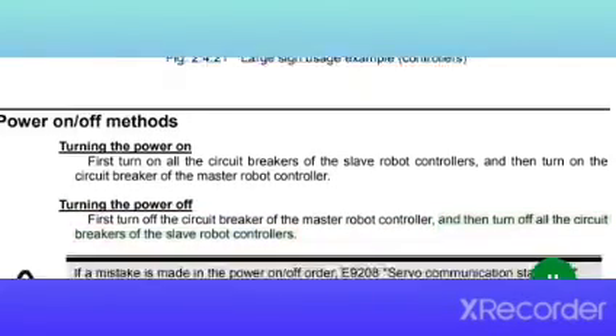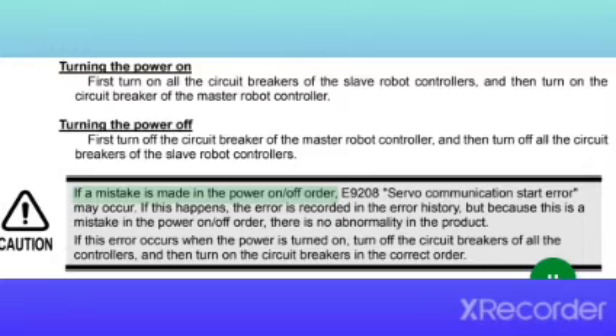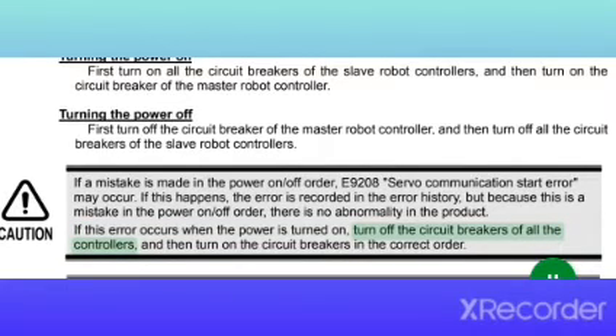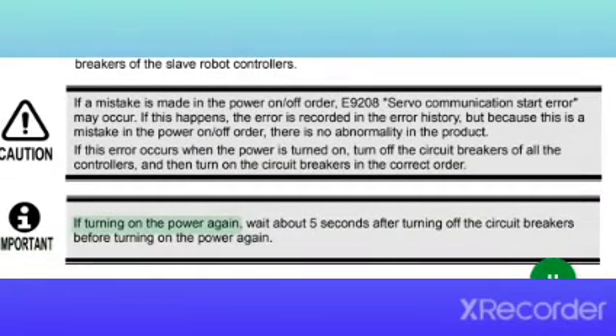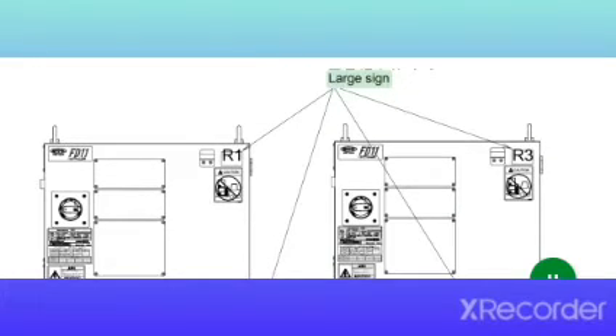Caution: if a mistake is made in the power on/off order, E9208 servo communication start error may occur. If this happens, the error is recorded in the error history, but because this is a mistake in the power on/off order, there is no abnormality in the product. If this error occurs when the power is turned on, turn off the circuit breakers of all the controllers, and then turn on the circuit breakers in the correct order. Important: if turning on the power again, wait about 5 seconds after turning off the circuit breakers before turning on the power again. Large sign. 2.5 Parts replacement procedures, 2 to 27.